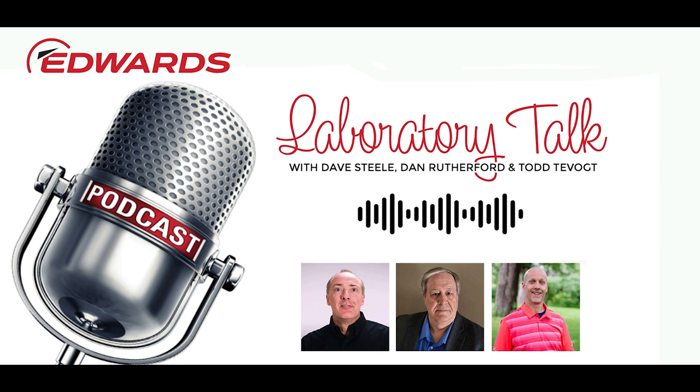So back to the gauges themselves. The Edwards active gauge heads themselves are all powered from a simple 24 volt DC power supply, nothing sophisticated or complicated, just a regular DC power supply. And the output is 0 to 10 volts that represents what the pressure is. Because you don't actually need a separate controller to make any of that work, it's all built into the gauge head, you can integrate that into a piece of equipment if you want to.